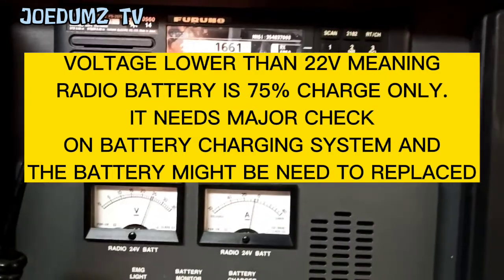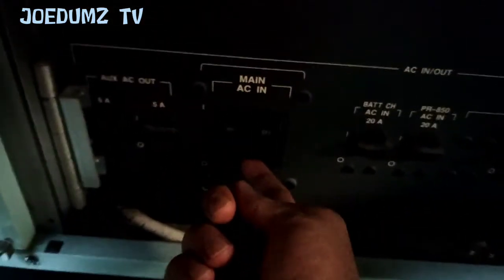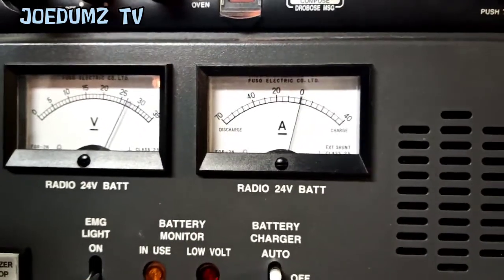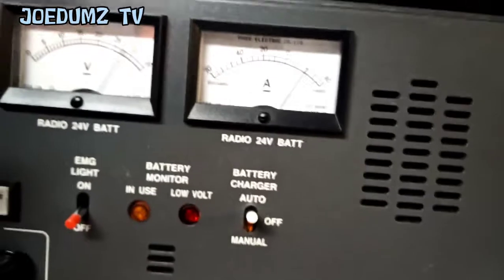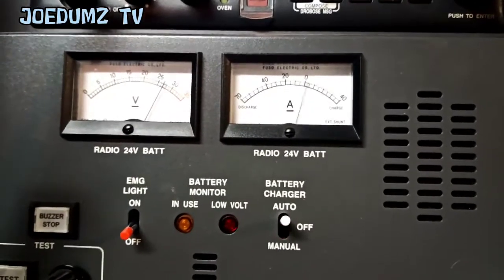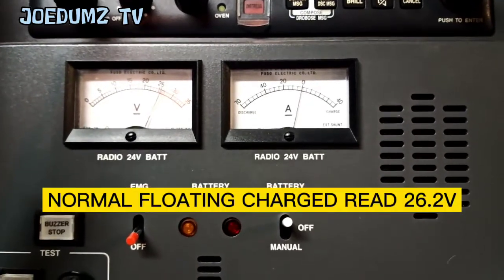That is how to check offload and onload. And don't forget to switch back on the main AC power, so the battery could have a chance to recharge. Now it is going up and recharging. But the recharger is on auto. When it is already full charge, it will keep floating charge around 26 volts.